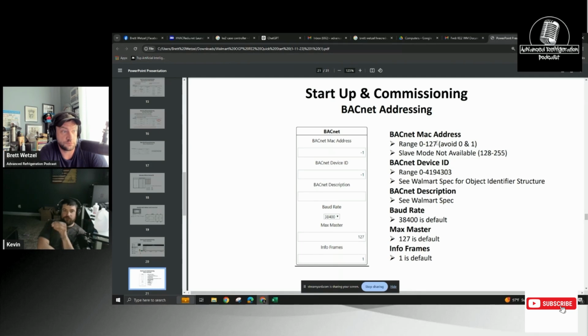Max Masters was set to 10, but we had 20 case controllers, so it would only bring on the first 10. It wouldn't read the rest of them. We had to make sure that setting is higher than the number of case controllers you have, or else you'll never be able to bring them all in.